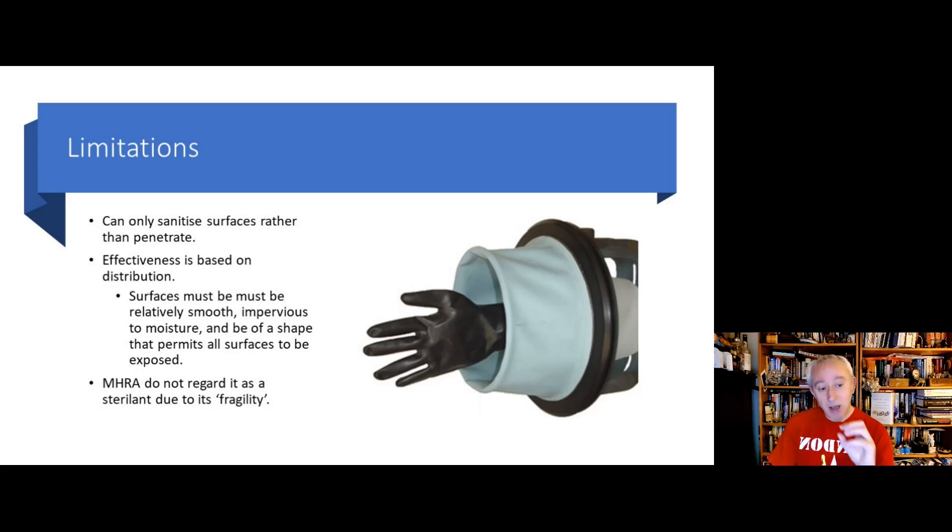However, it is limited. And the reason it's limited is that unlike a lot of other sterilization methods where you can penetrate the item that you want to sterilize, hydrogen peroxide only treats the surface. So unlike steam, dry heat, radiation, ethylene oxide, which can all penetrate, then hydrogen peroxide can only decontaminate the outside, which is one of the fundamental reasons why it's not called a sterilization technology.